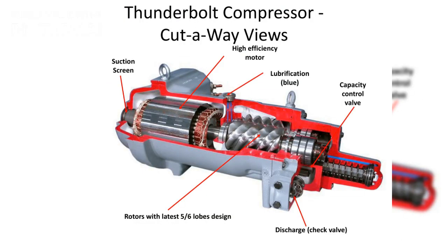Patented rotor profile principle, geometry direct drive operated. The serviceable screw can be replaced upon damages or non-compression issues. Fifth, high-strength motor for star delta or direct star type starter. Sixth, high motor efficiency. Seventh, motor cooling is achieved by the cooled suction refrigerant. Slip fit for serviceability.